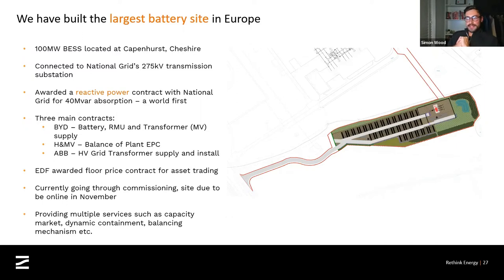We built this site off the back of being awarded a reactive power contract with National Grid. As part of that contract, we are required to provide a service, which means we need to absorb a certain amount, that being 40 MVAR, of reactive power. And I'll leave it to Mike to go through the technicalities of exactly what that means.